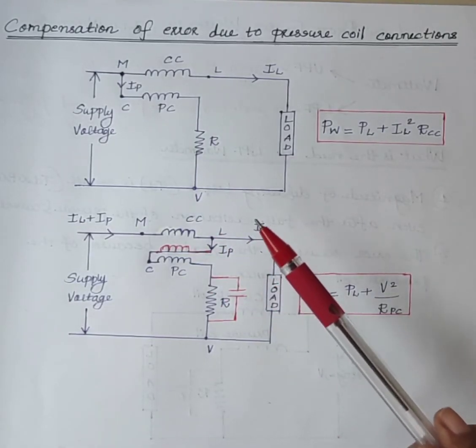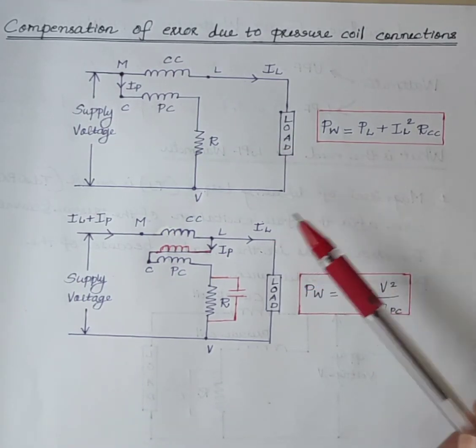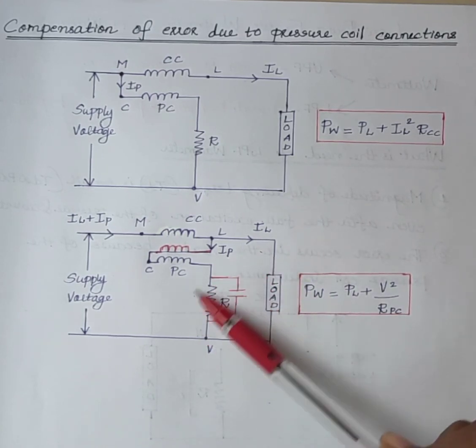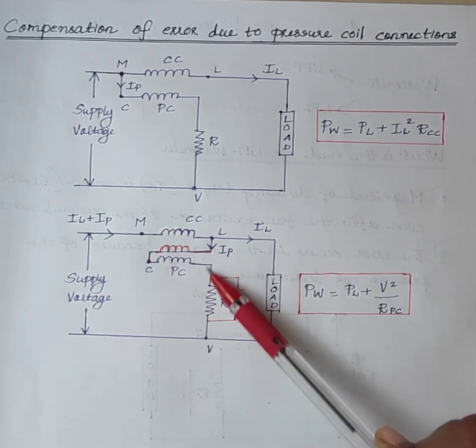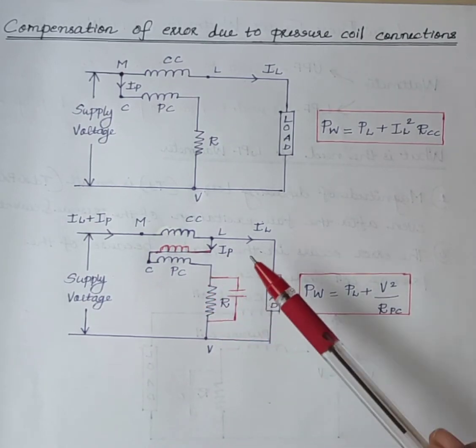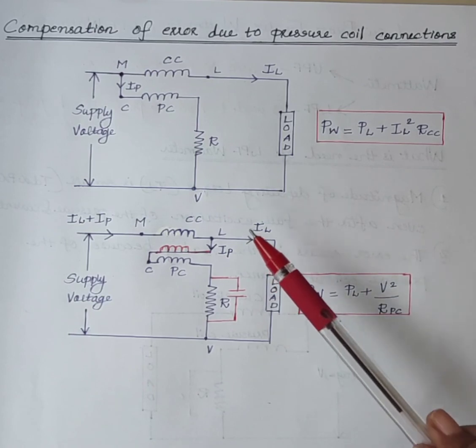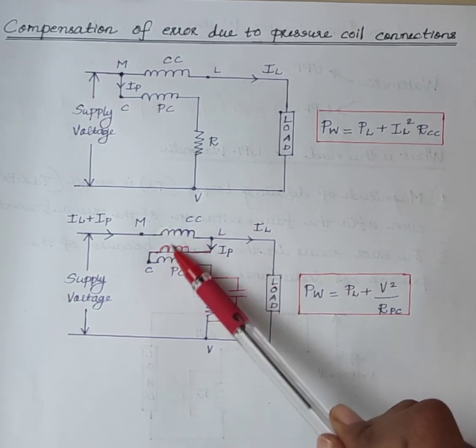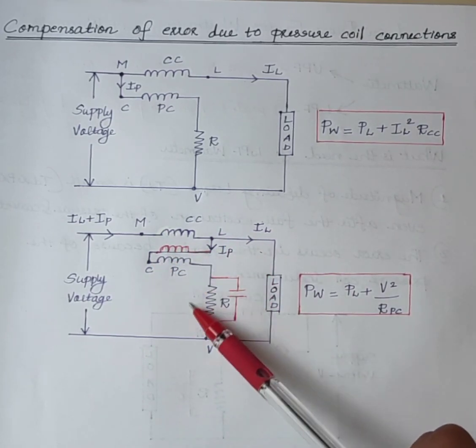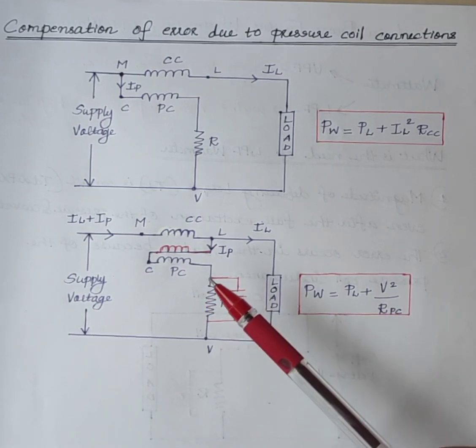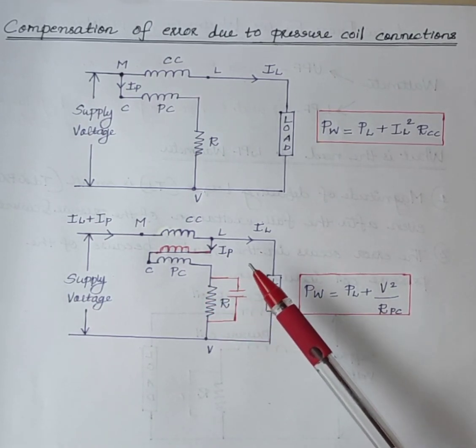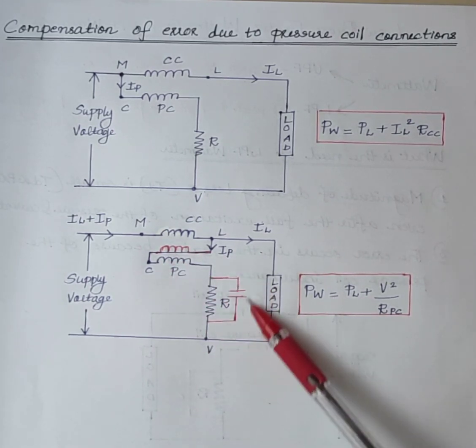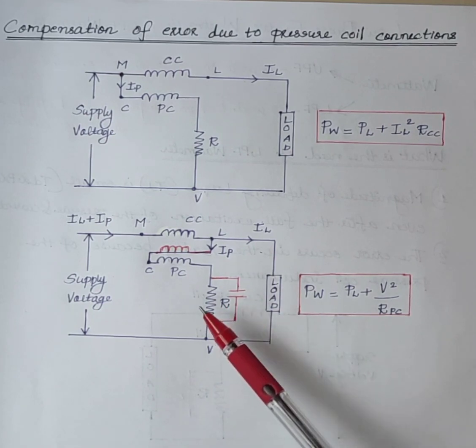From this discussion, we can make three main conclusions. First, in a low power factor meter, in order to increase the deflecting torque, a low resistor is connected in series with the pressure coil. Second, in order to compensate the error due to pressure coil connections, a compensating coil is connected in series with the pressure coil. Third, in order to compensate the error due to pressure coil inductance, a capacitor is connected in parallel with the series resistor.